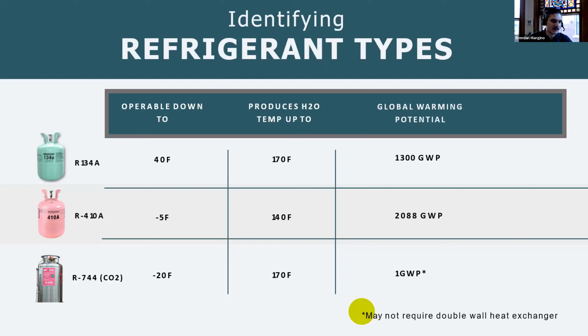The second refrigerant is R410A. This can operate at a colder ambient temperature, -5 degrees Fahrenheit, or even a little bit lower with some of the more modern systems, but it can only produce hot water up to 140 degrees Fahrenheit. And that's really the upper echelon of this refrigerant. A lot of them are 130. And when you start factoring in heat exchangers, it's even going to be less than that. So typically you would need supplemental electric resistance to boost that temperature up to our target. This also has the highest global warming potential out of the 3 refrigerants we're going to look at.